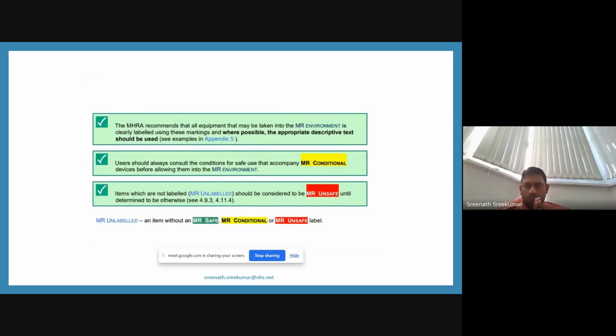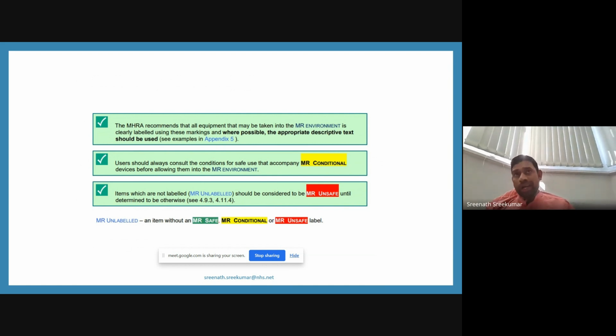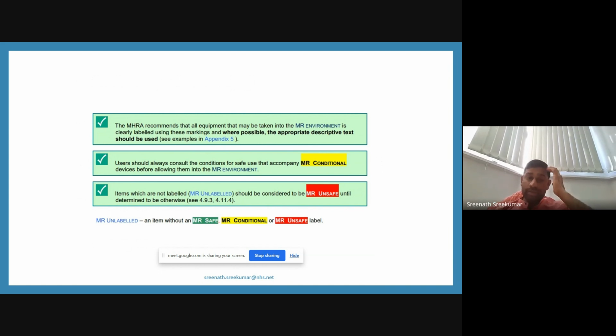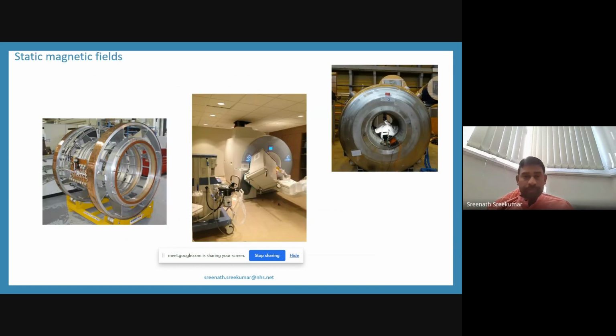Then we go to the MHRA recommendations. The MHRA recommendation says we can only allow devices that are conditional within the MR environment. Anything unlabeled should be considered MR unsafe. So only devices labeled as conditional or MR safe should be allowed inside the scanner room or MR environment. Otherwise, they are not allowed and are considered unsafe.